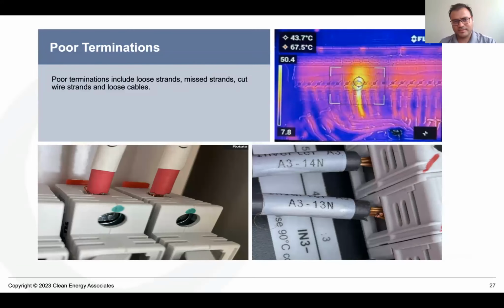All right, this is one of the other issues, poor terminations. The string of PV modules or solar panels are connected into the inverters. And these are the cables from the string of PV modules going into the inverters and terminated into a fuse block over here. If you expand the picture, if you look at both the bottom pictures very closely, you can see a copper cable, a copper strand showing out of the terminal block.